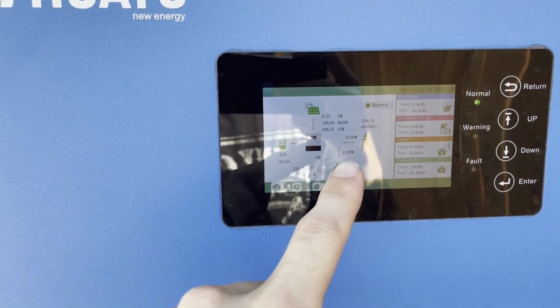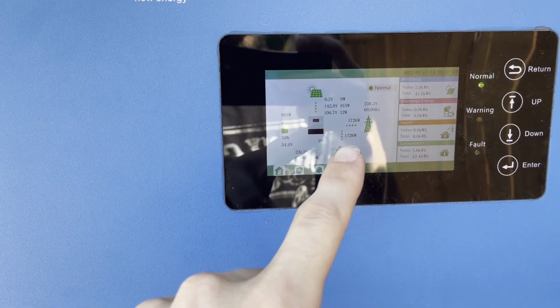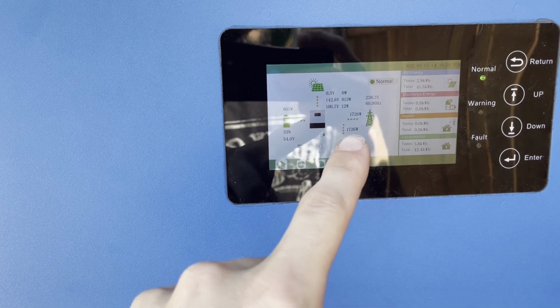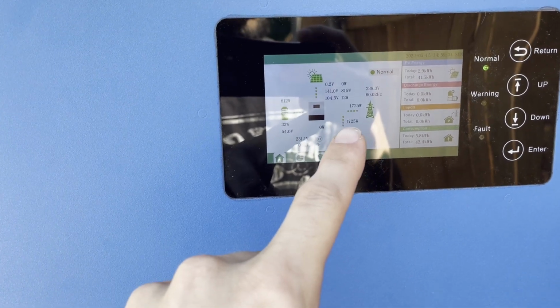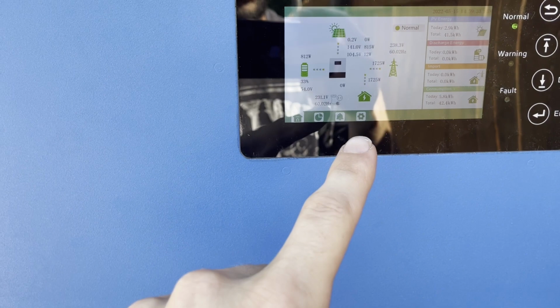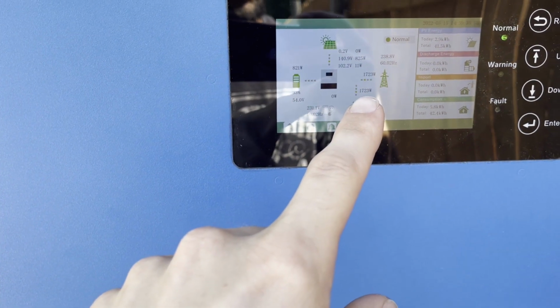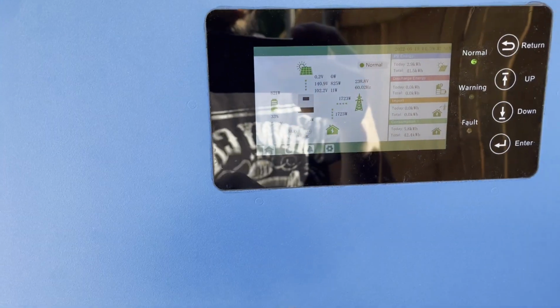It started about 1,000 watts this morning and it's up to 1,700. This would get up to about 2,500, it's a 3-ton unit before it maxes out. So it's nice to know it's not maxed out, we've actually got some cooling capacity we're not using.